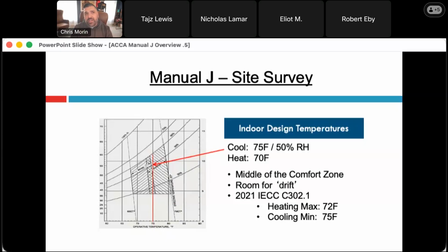What I want you guys to know and be able to explain is why these design conditions, because every homeowner is probably going to say they want it to be 67 in their house, right, in cooling. And it's just not possible with residential systems. And it does not allow room for drift under the other 98% of the design temperature year, right? So if you size to a maximum temp, in this case at 100 degrees, 99 point something percent of the year, we're oversized 99% of the year. So when that system needs to ramp down, hopefully it's variable speed, it needs to be able to still maintain in this comfort zone on your psychrometric chart right here.